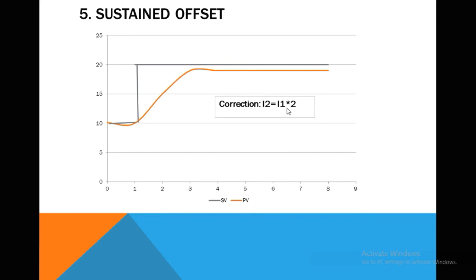So of all these 5 steps, you see which is relevant for this particular context, make that change and then again make a set point change and see the response. So by doing it 2-3 times you can properly tune the controller. You don't require any data collection software, no supervisory controller, no nothing, just your DCS panel.